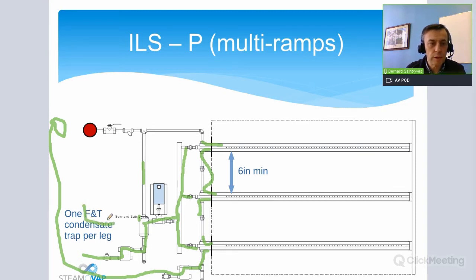And you will need one condensate trap. F&T means float and thermostatic. Some others will use inverted bucket. We are using a float and thermostatic steam trap. Okay, the minimum distance between the different manifolds would be 6 inches. Why? Because you need to have a union in between each of the ramps, and you need the space for this. Of course, all this will be assembled on site by the contractor.